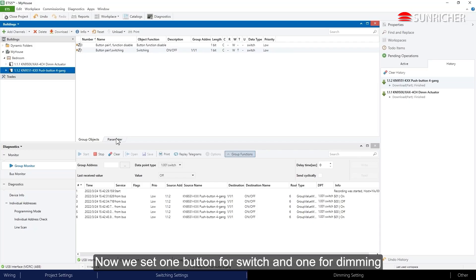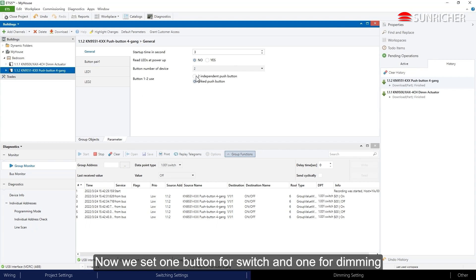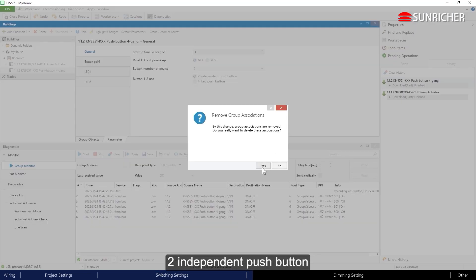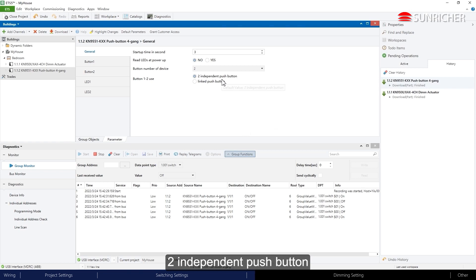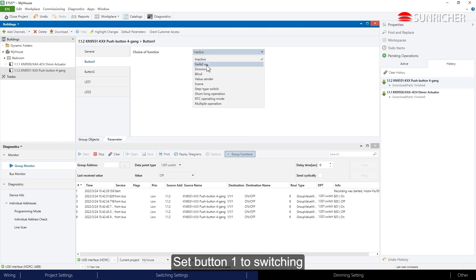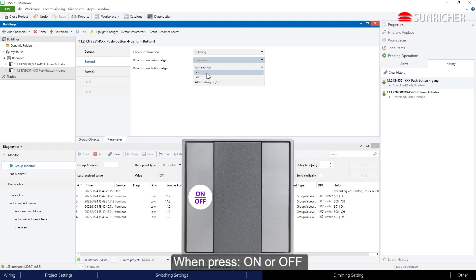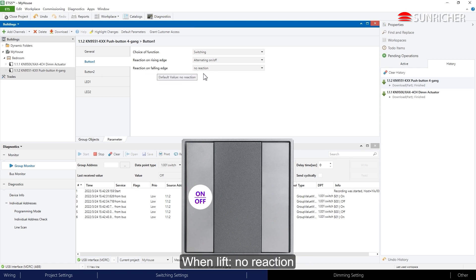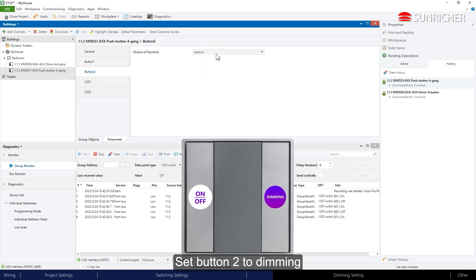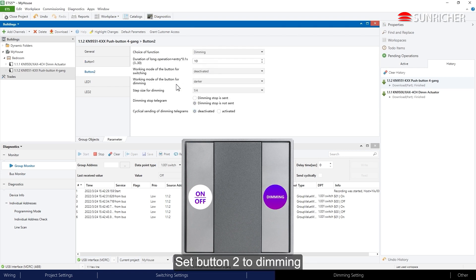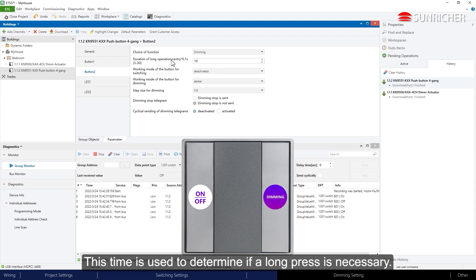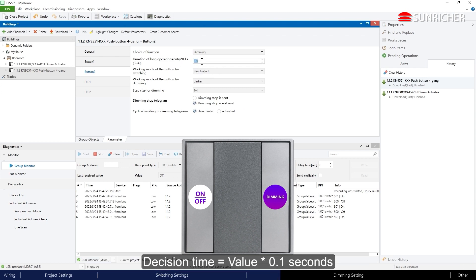Now we set one button for switching and one for dimming — two independent push buttons. Set button one to switching: when pressed, it toggles on or off; when released, no reaction. Set button two to dimming. The decision time determines if a long press is necessary — decision time equals value times 0.1 seconds.